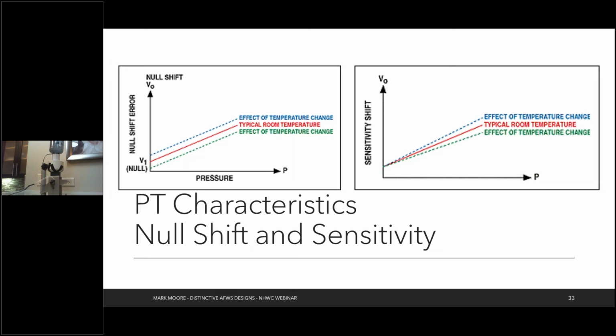So one thing you have to be aware of is these null shift and sensitivity changes. And when I say be aware of, it's more that when you do these calibrations, this might be a reason your calibrations are showing bad data. This might be a reason that a PT fails its calibration, because there's some sort of null shift that's not being accounted for because something on the PT itself has failed.